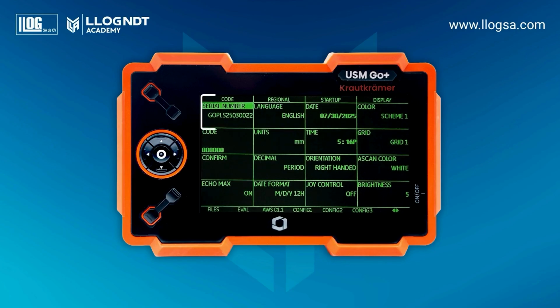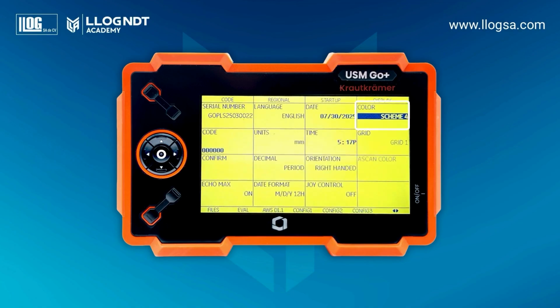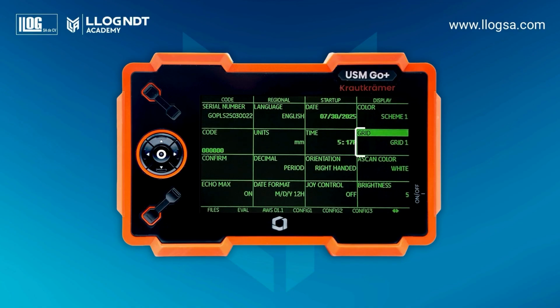serial number, enabling advanced functions using a code, confirming the entered code, showing maximum amplitudes, changing the language, measurement units, choosing point or comma as the decimal separator, adjusting the date format, setting the date, time, display orientation, joystick lock, and color scheme. There are 4 available color schemes, 2 for indoor use and 2 for outdoor use. You can also configure the type of grid, the A-scan color, and finally, the display brightness.